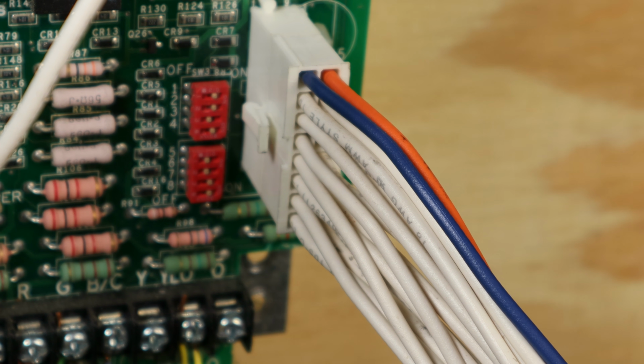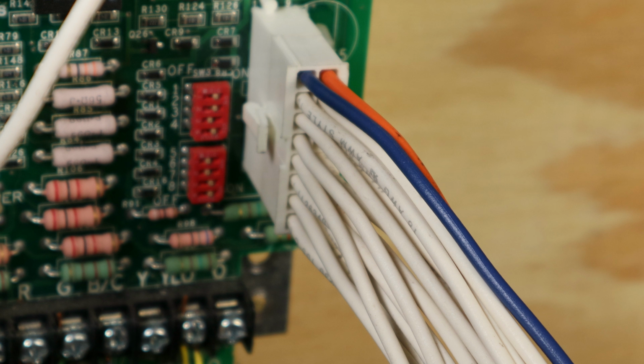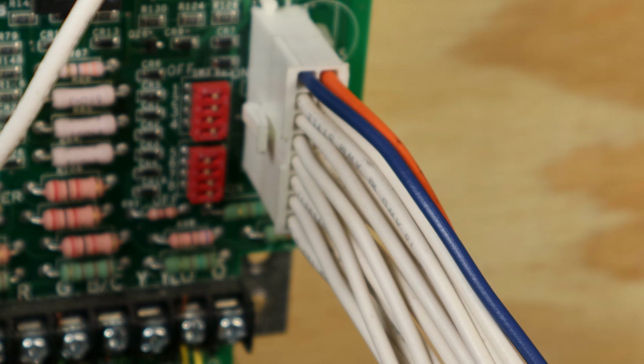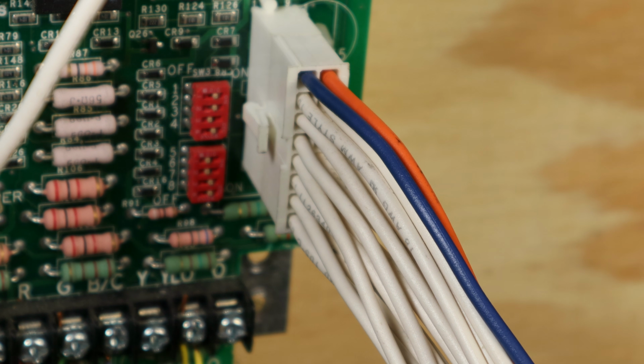Now, this microprocessor is communicating with the module on the motor itself through all these white wires here. So what we're talking about is a low DC voltage power that powers the ECM module's logic. We have speed and torque commands, what airflow targets to hit. We have feedback and status. We can keep track of the motor RPM, the torque load, fault statuses, things of that nature. There's constant communication and readings back and forth between the module and this microprocessor. That's why we go through all the trouble of cleaning these signals up and making them nice and steady, because any fluctuations can lead to misreadings between the module and the control board.